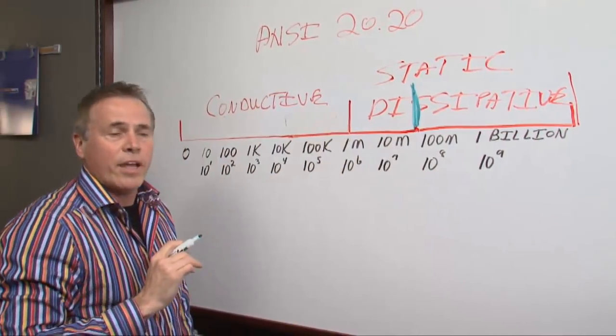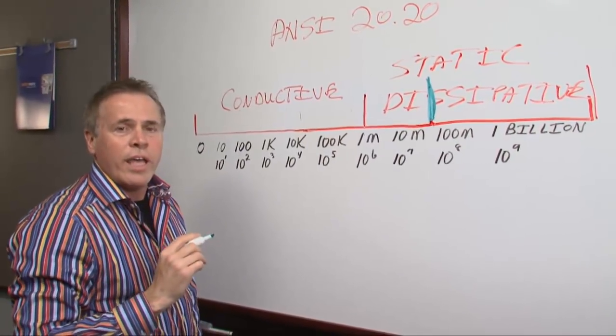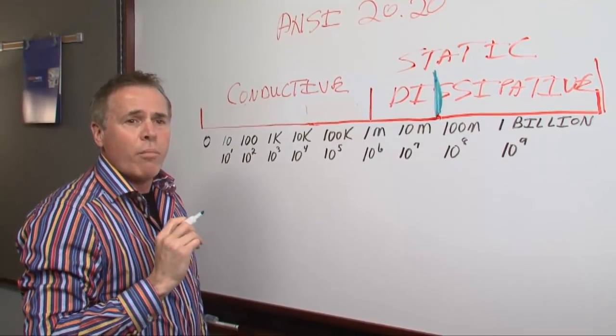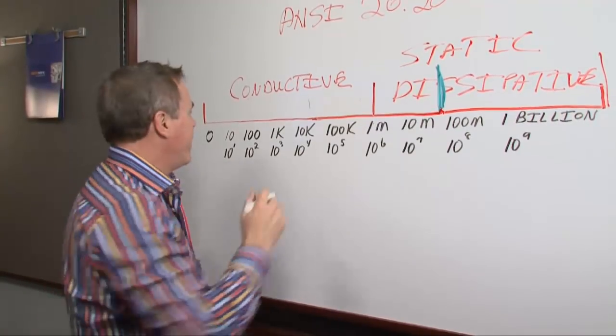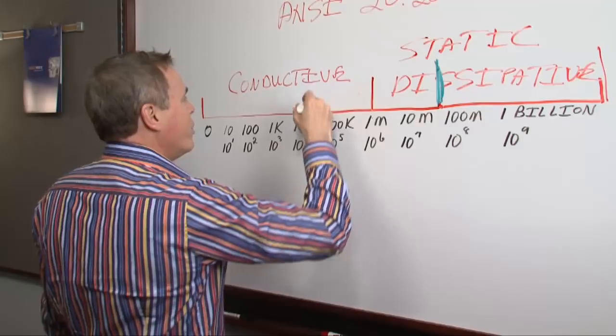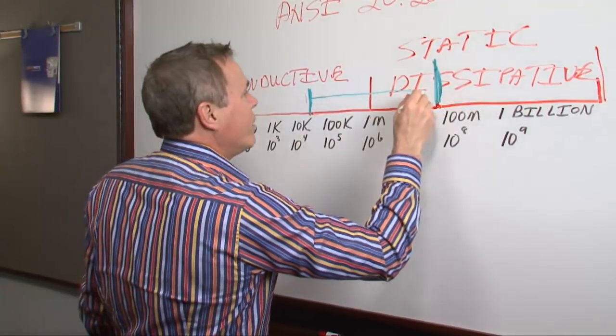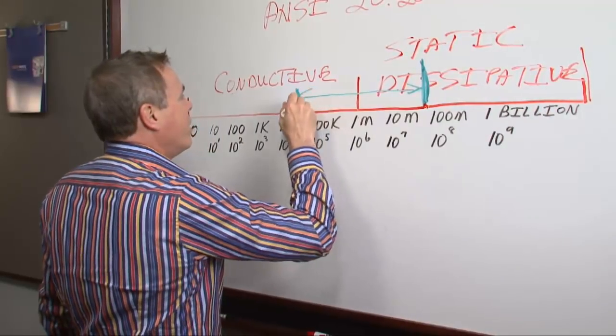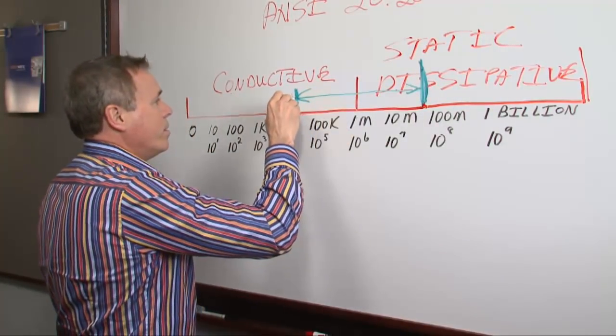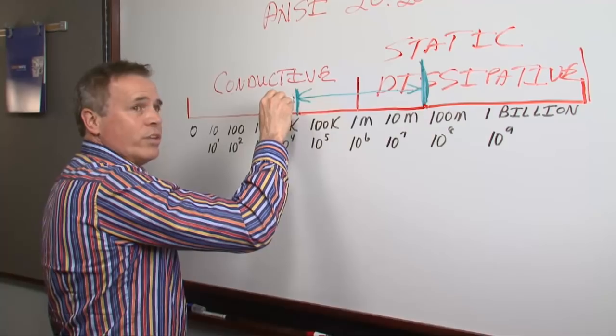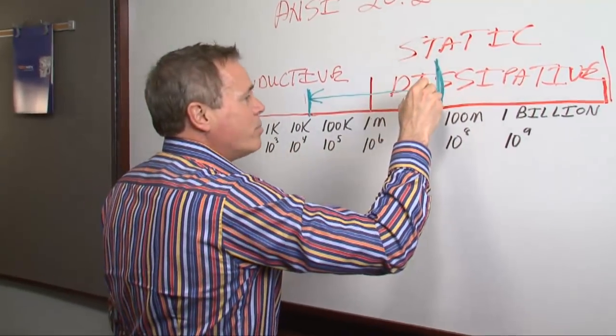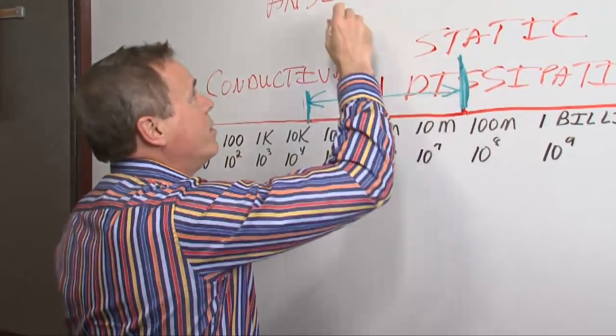The NFPA and OSHA say that the floor has to have always more resistance than 25,000 ohms. Well, here's 10,000, here's 100K. So here's 25,000. So in between here and here, we have the lowest margin where you're still safe.